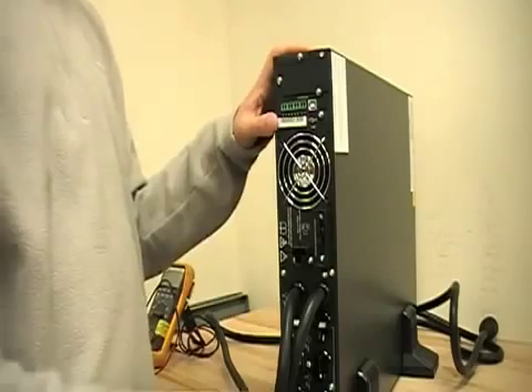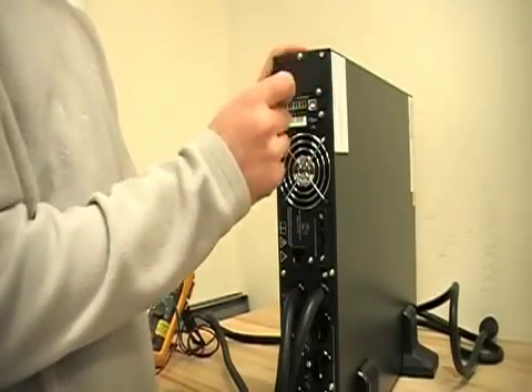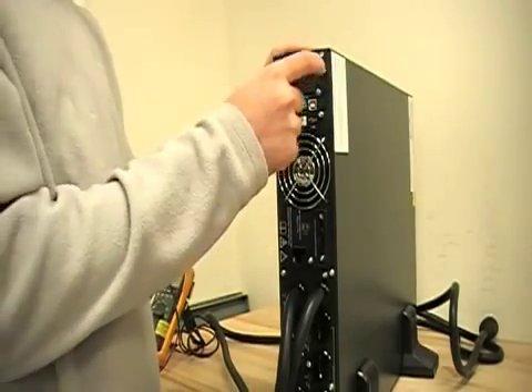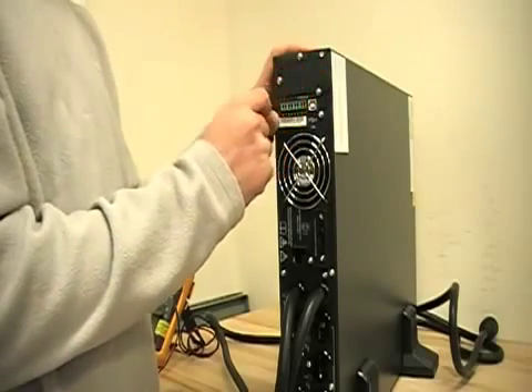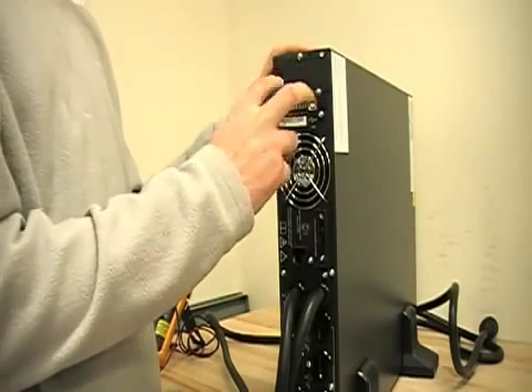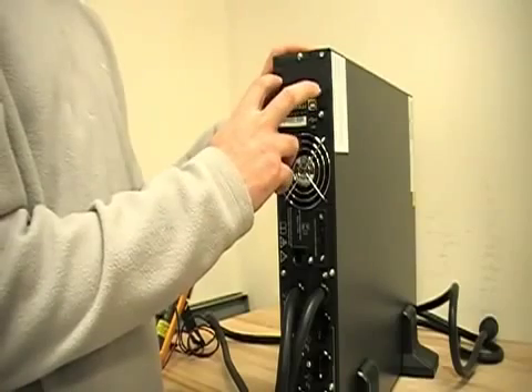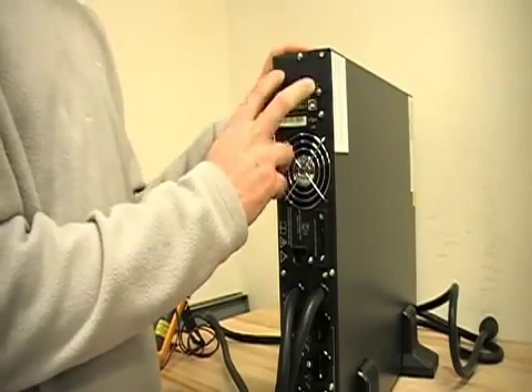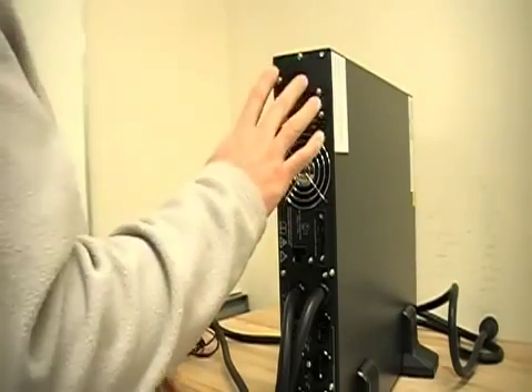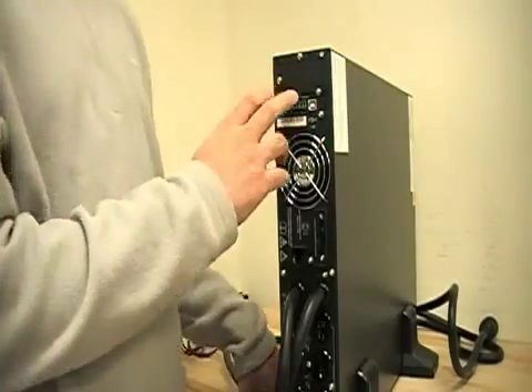If you're changing a unit out, you'd have to unplug and unwire the alarm card, whether it be a 25 pin connector or the Phoenix connector blocks. Before you insert the card, make sure the jumpers are installed or not installed according to the drawings for your alarm card. For our purposes, all the jumpers usually come off the alarm cards.